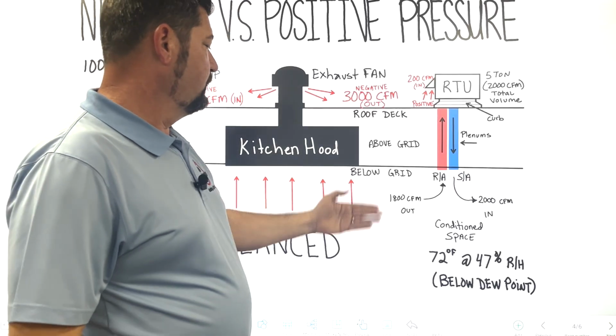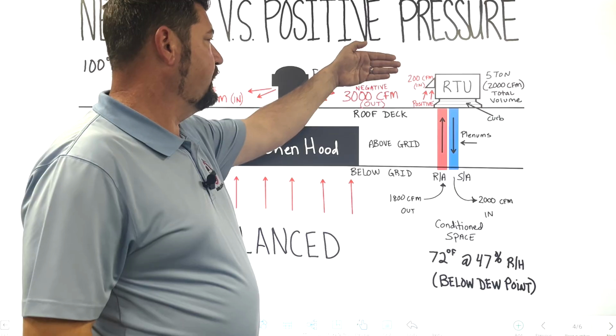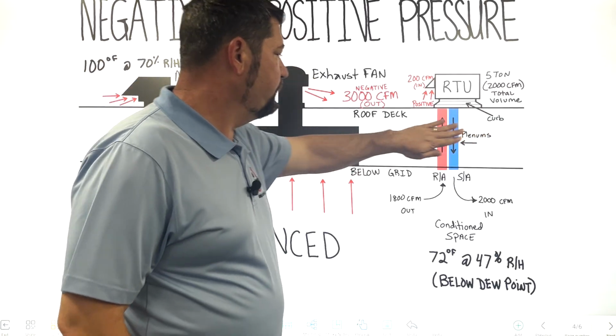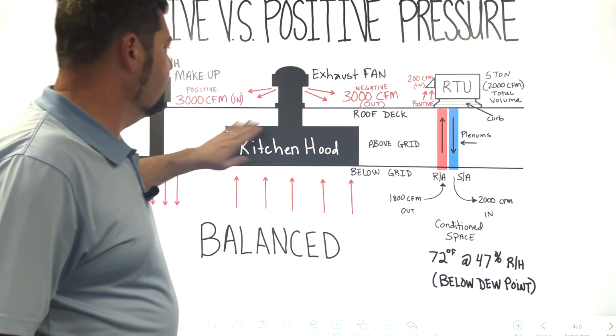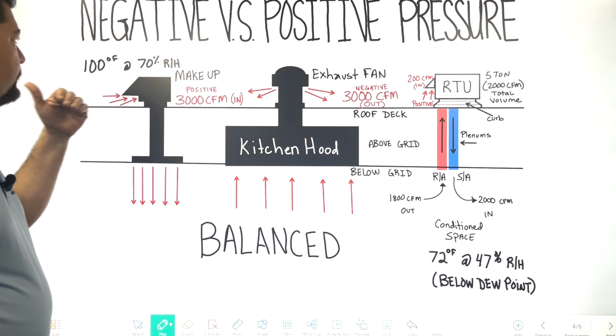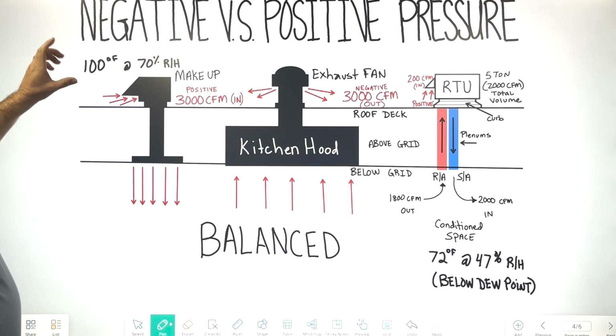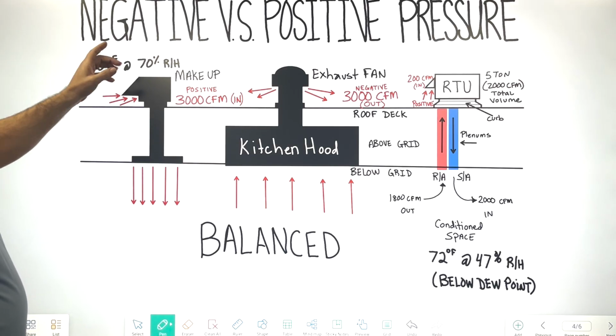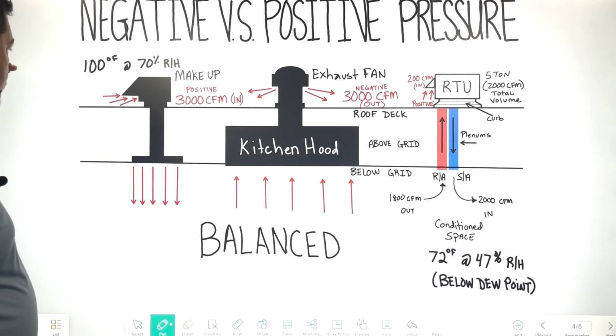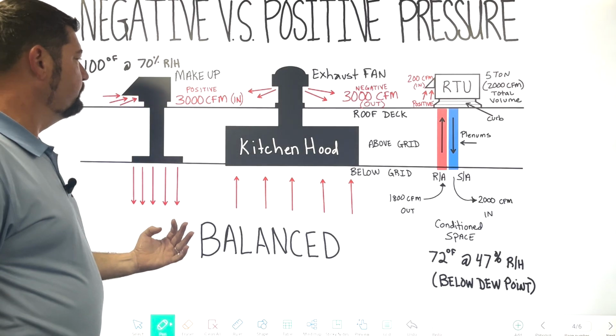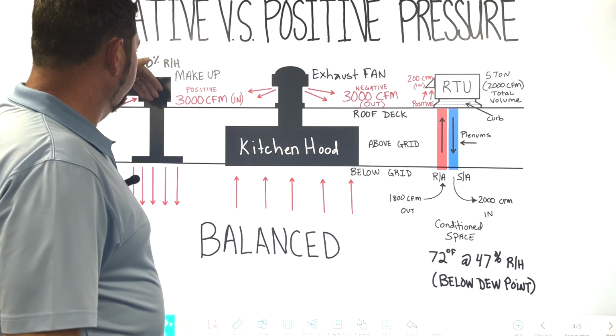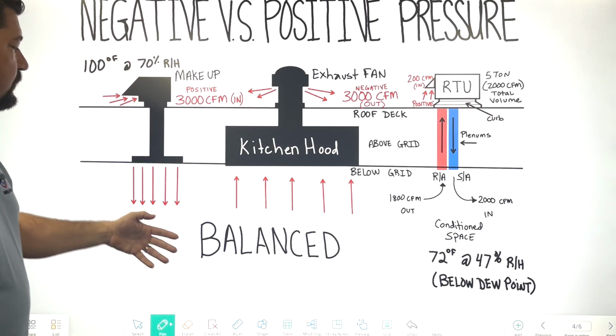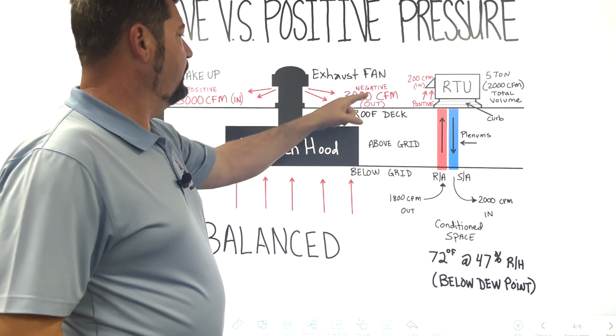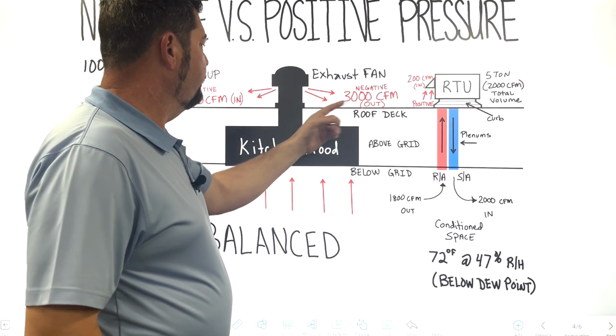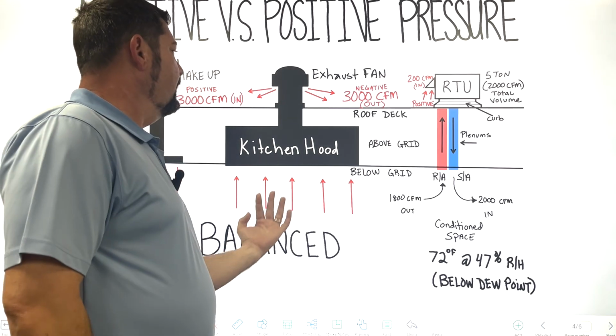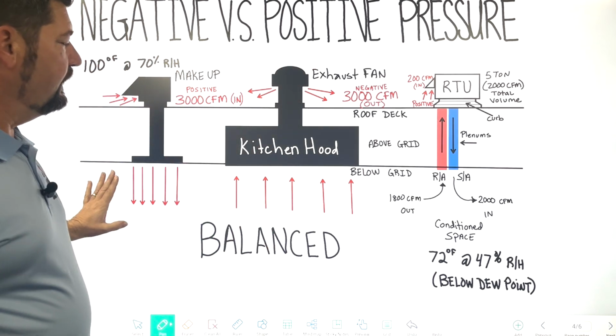3 different temperatures: a low temperature, a higher temperature, a very hot temperature, right? We're not really concerned with the temperature above the ceiling grid right now. But if you look at some of these temperatures that I wrote down, we have 100 degrees on the roof deck at a 70% relative humidity, right? And we're pulling that in. And that's not creating a problem because we're bringing in 3,000 CFMs of positive air into the kitchen, and then the exhaust fan, all right, that's a negative 3,000 CFMs out. So it's 3,000 CFMs in and 3,000 CFMs out. So it's unchanged and it's balanced.